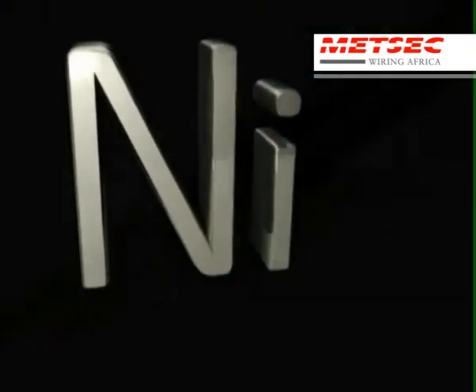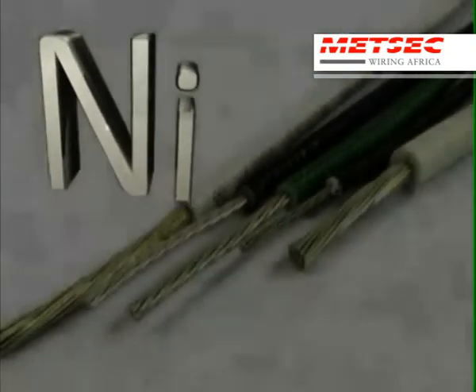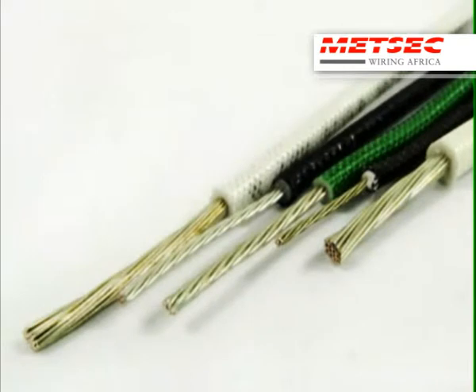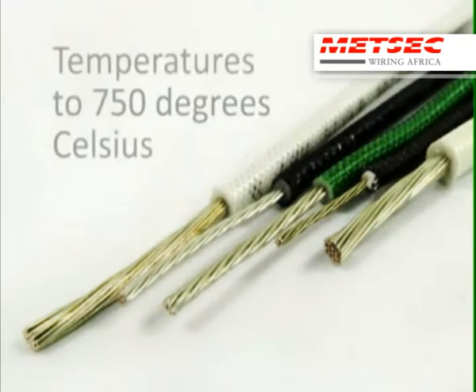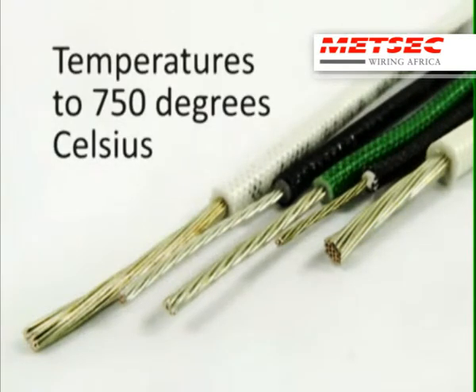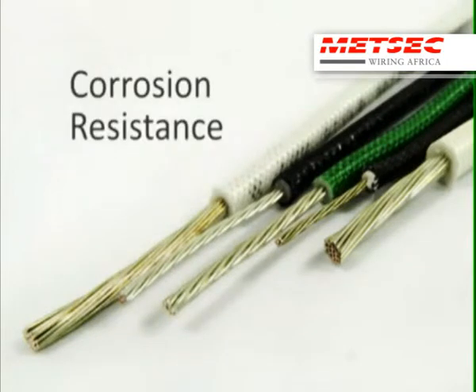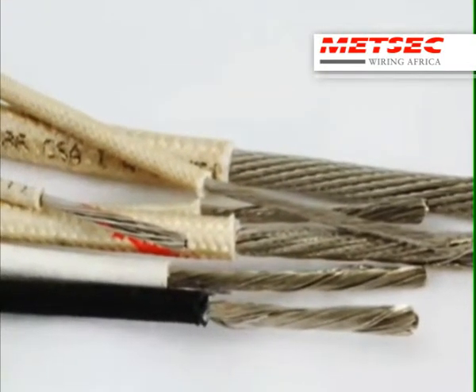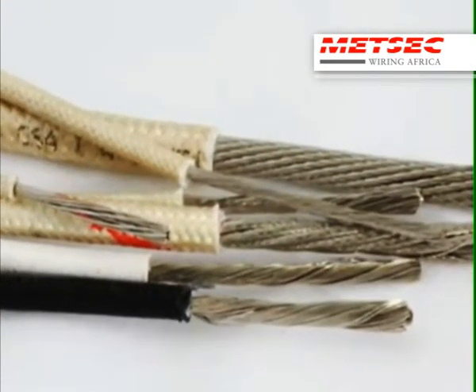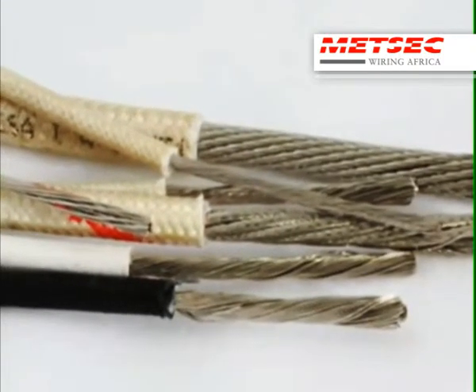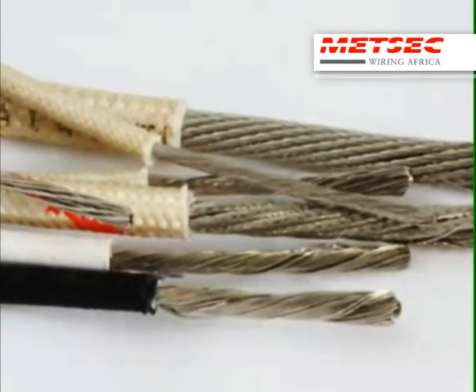Nickel-plated wire also operates in extreme conditions and over a wide temperature range. If the nickel plating is thick, it can withstand temperatures up to 750°C. Nickel also adds a layer of excellent corrosion resistance. High-strength alloys are other materials commonly used as conductors. These are typically silver-plated or nickel-plated as well.